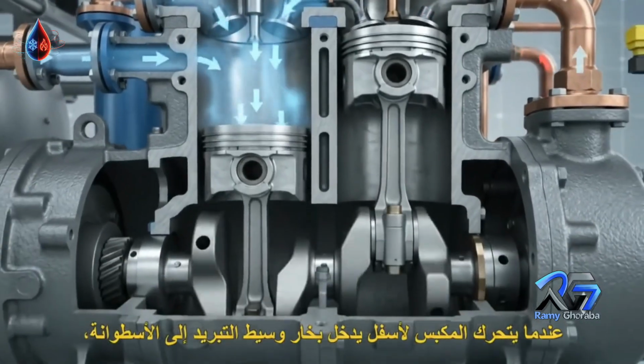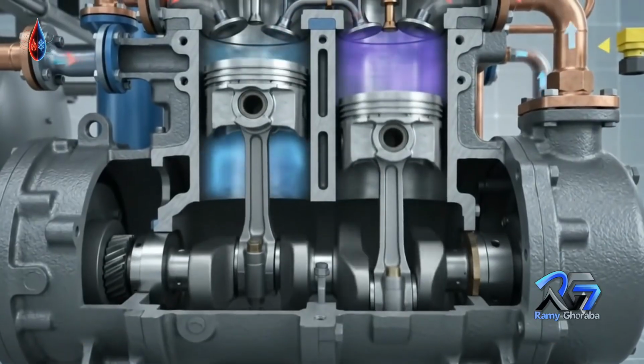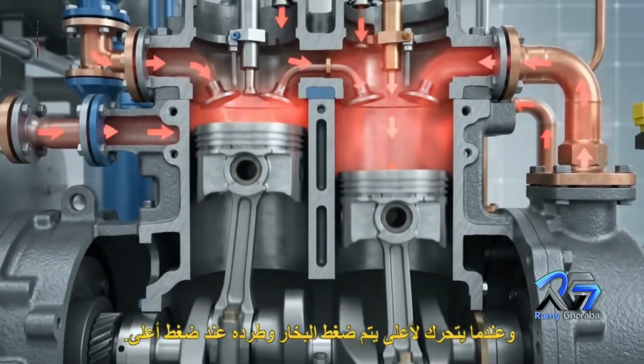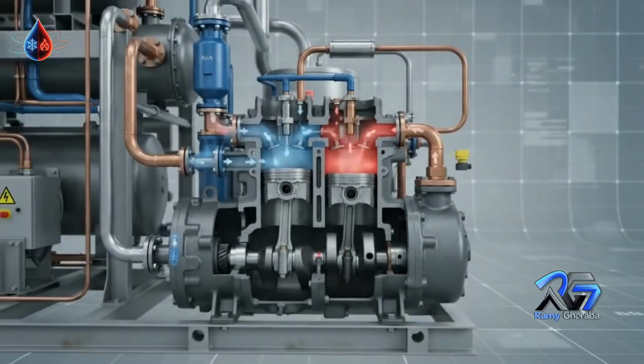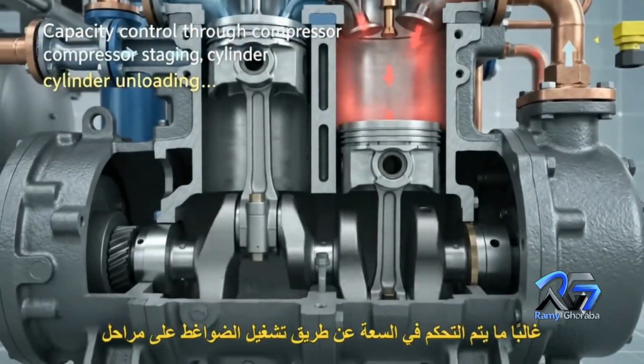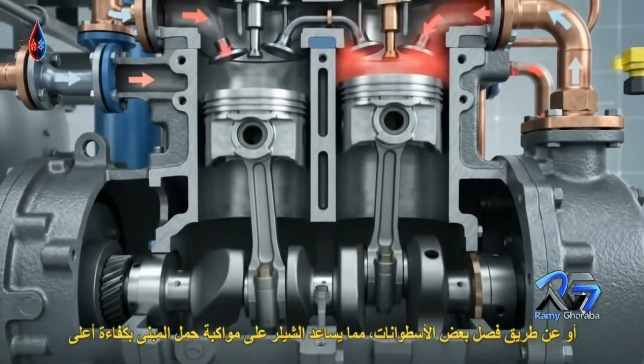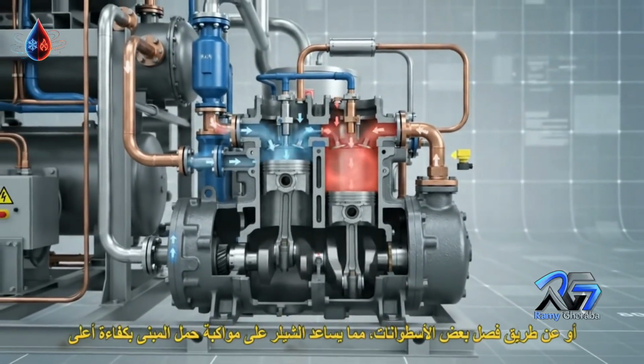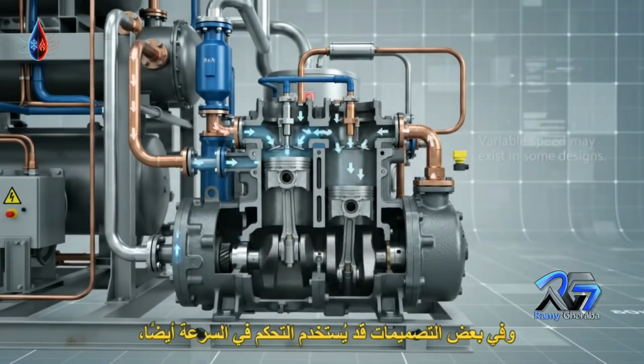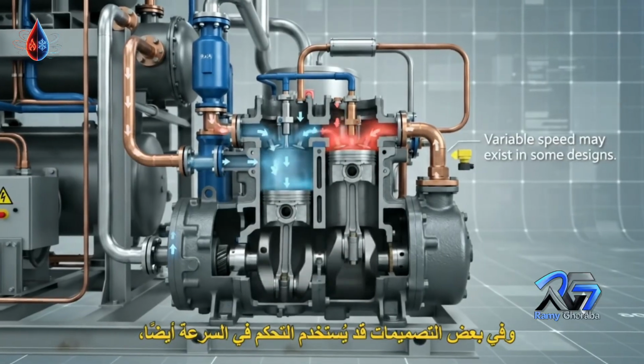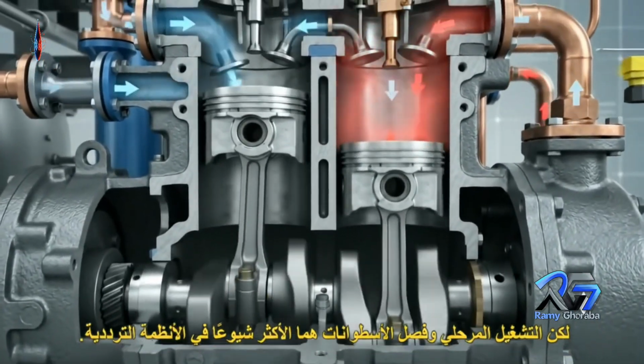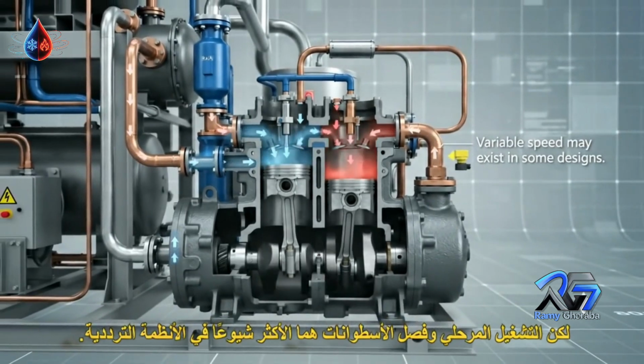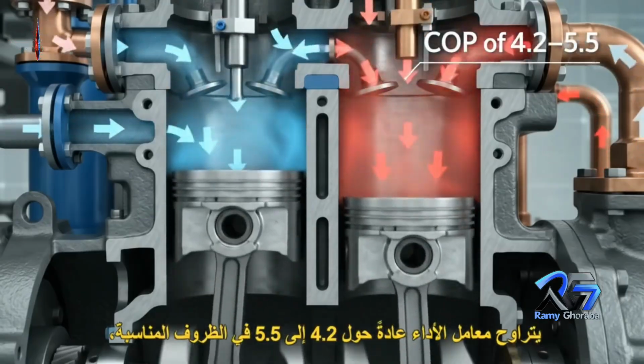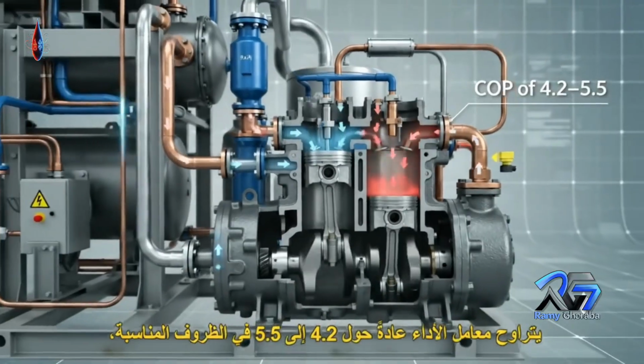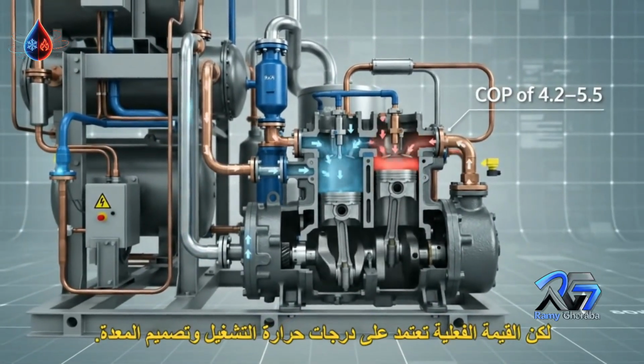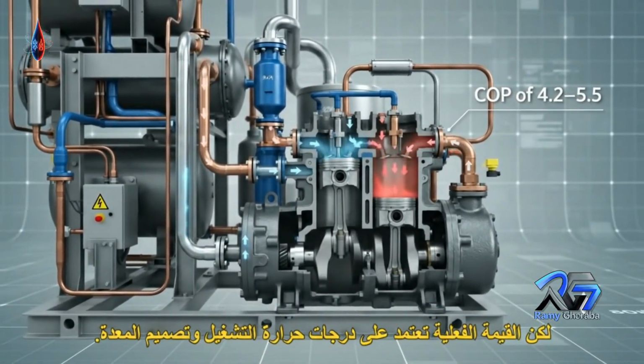As the piston moves down, refrigerant vapor enters the cylinder. As it moves up, the vapor is compressed and discharged at a higher pressure. Capacity control is commonly achieved by compressor staging or cylinder unloading, which helps the chiller match the building load more efficiently. In some designs, speed control may also be used, but staging and unloading are the more common control methods for reciprocating systems. The COP typically ranges around 4.2 to 5.5 under suitable conditions, but the actual value depends on operating temperatures and equipment design.